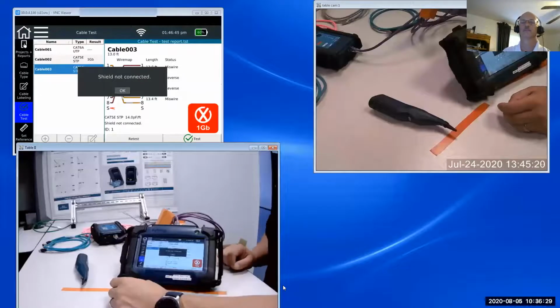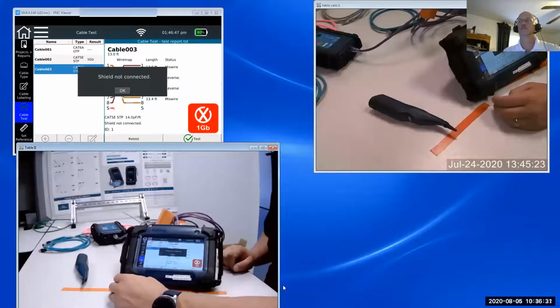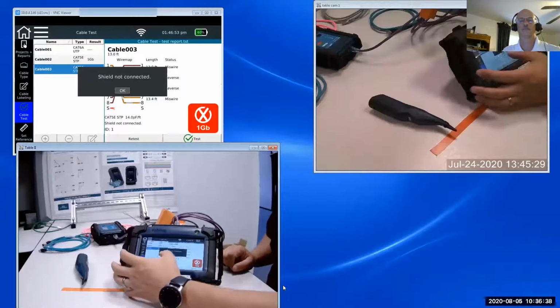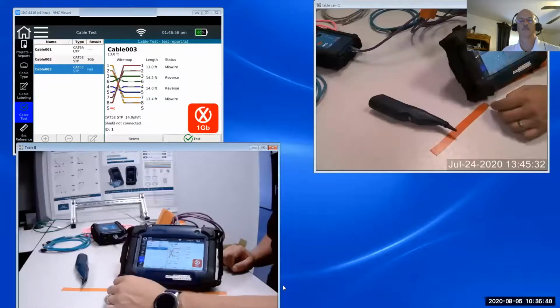Okay, so we got a couple errors here on this cable. Number one, I can see that the shield is not connected. This test was looking for a shield, the shield was not connected, and it's failed on that. It would fail on that reason alone. But also, I've got a number of miswires in here. You can see that conductor 1 is not going across to the other side as it should — it's going down to 8. It looks like everything is crossed on this cable. This cable is not wired correctly and would be a problem. The tester picks that up easily.